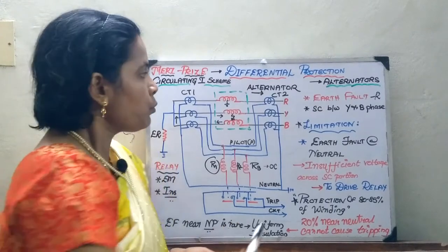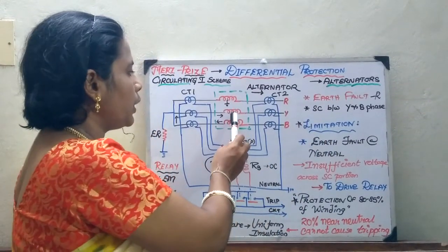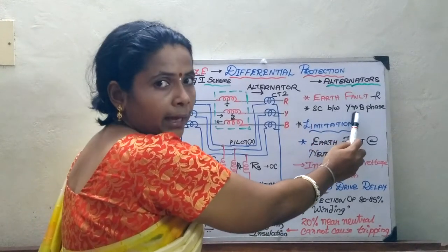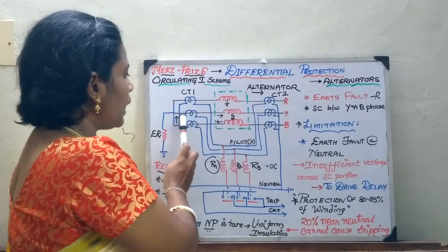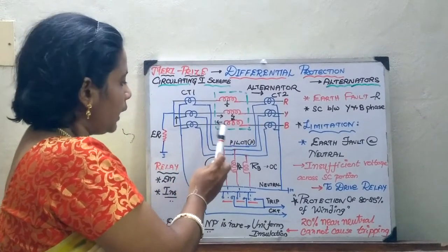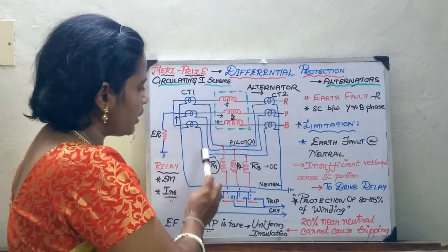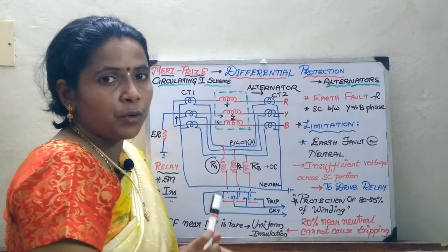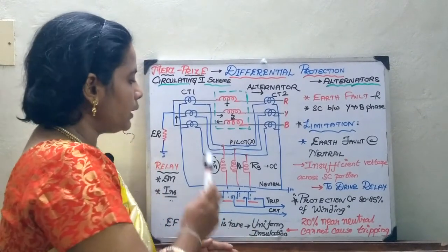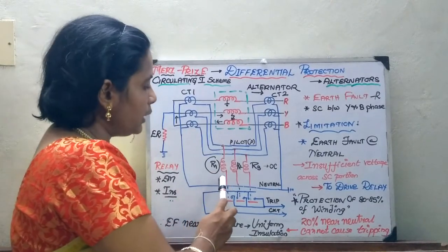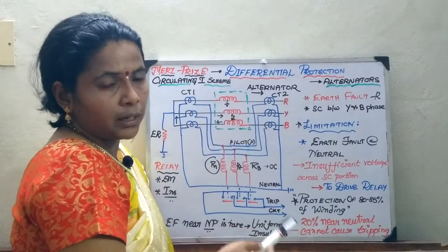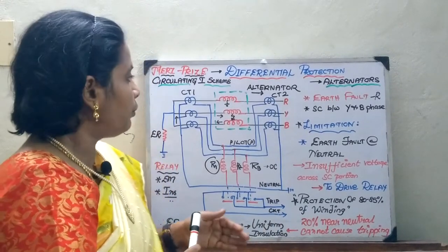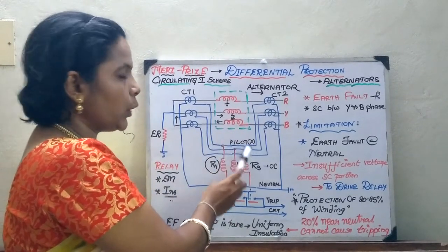Now consider a short circuit between the Y and B phases — a phase-to-phase fault. In this case, the current circulates through the Y phase winding and the B phase winding. As a result, relays R2 and R3 operate and trip the circuit. So if an earth fault occurs, relay R1 operates; if a phase-to-phase fault occurs, relays R2 and R3 operate and trip the circuit.